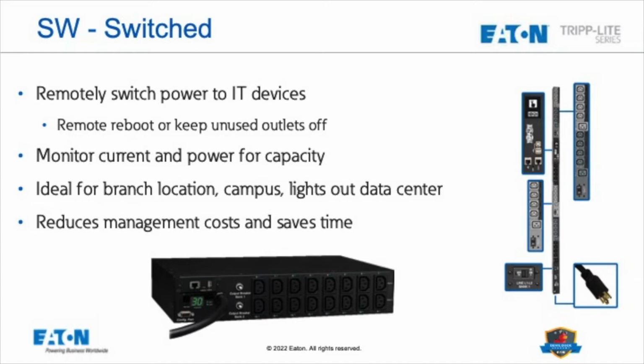And there was actually a story at a Wells Fargo data center. They lost power on their data center, and then when power came back, everything turned on at the same time. All the circuit breakers tripped. They turned them all back on. They tripped again. They were fighting it for like 4 hours until they figured out what was going on, but it was too big of a load coming on at the same time. So there's value in understanding when things like power sequencing can help.